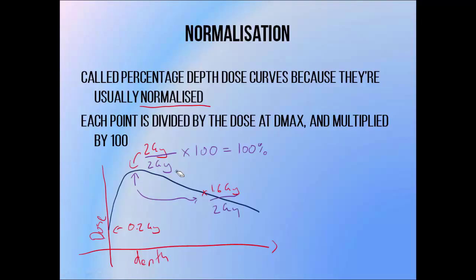This gives the dose at D-max a value of 100%, and the dose at every other point is expressed as a percentage of this dose. For example, 1.6 Gy is 80% of 2 Gy, so this becomes 80%, and 0.2 Gy is 10% of 2 Gy, so this becomes 10%. This is why it's called a percentage depth dose curve. The shape of a PDD curve depends heavily on the beam energy.